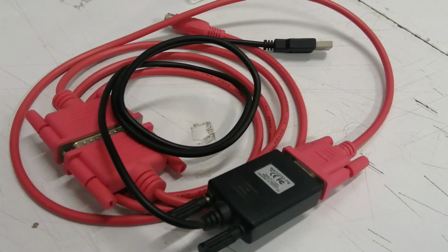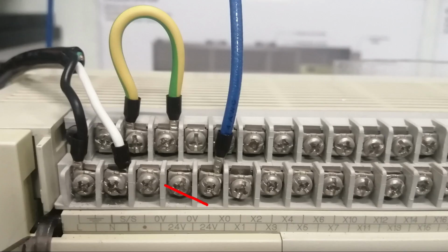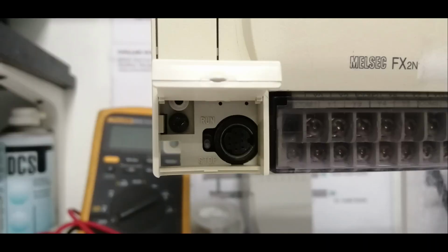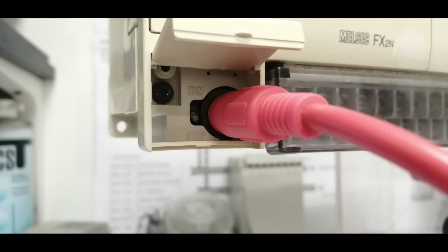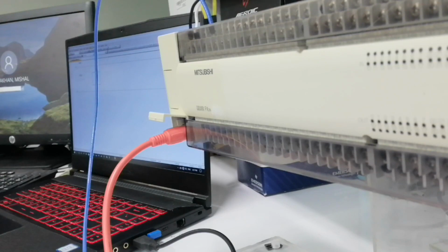To be able to upload or download a PLC program, we will use GX Works 2 software and a communication cable to connect the PC to the PLC. First, let's connect the 220 power supply, the S/S and 0 volts jumper wire, and the wire for 24 volts potential for the inputs. Then, connect the communication cable to the provided port, and connect it to the laptop via USB. Now, all things are ready, let's open up GX Works 2 software to begin.